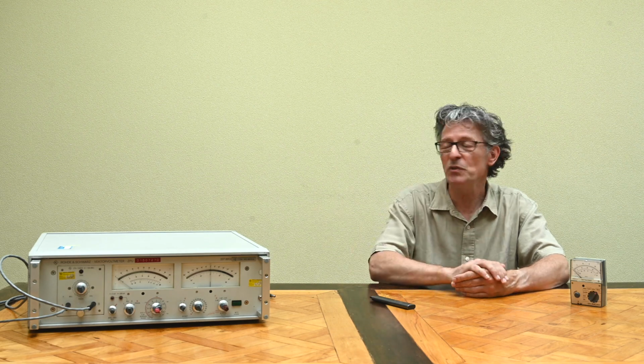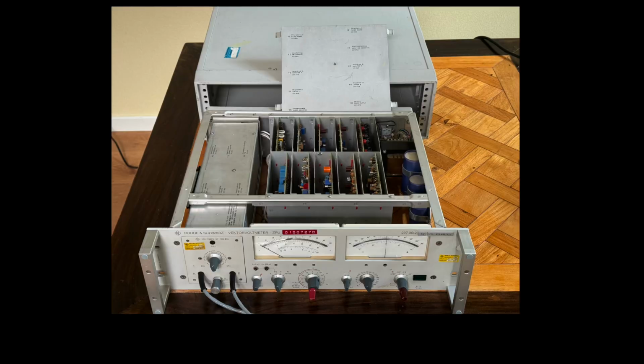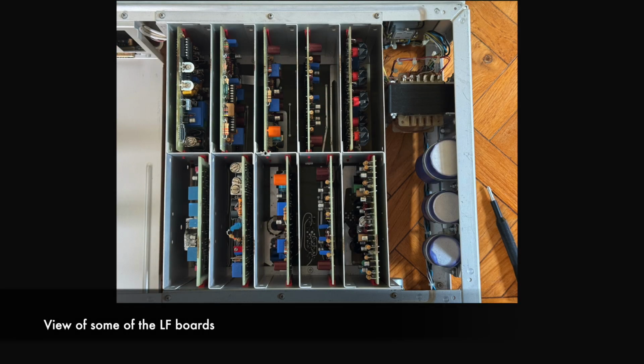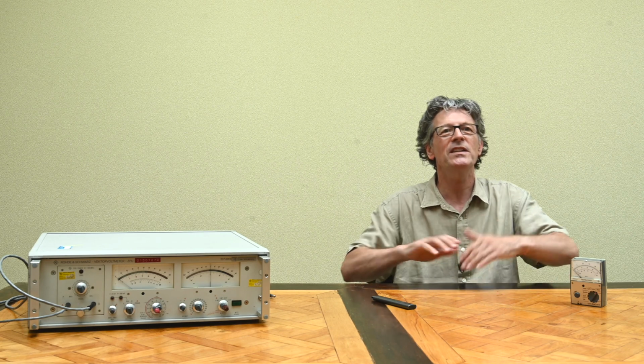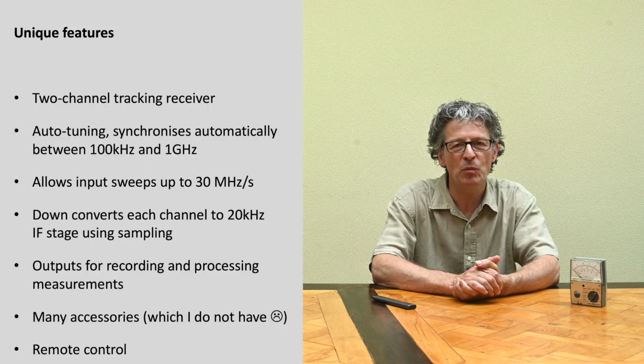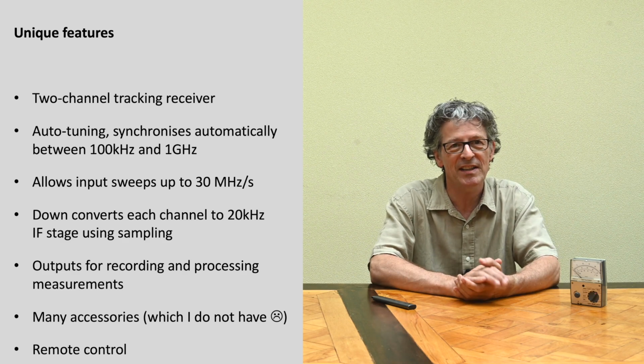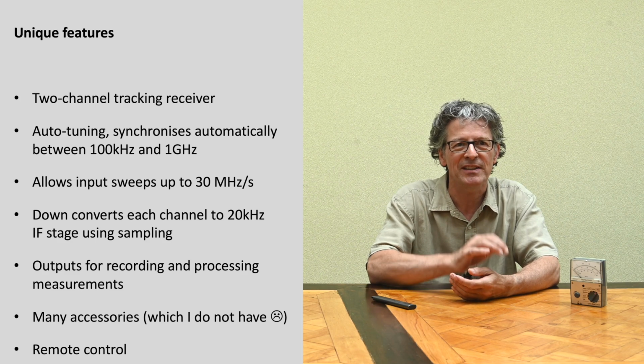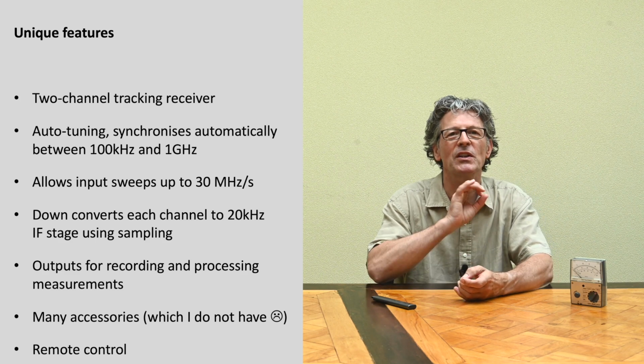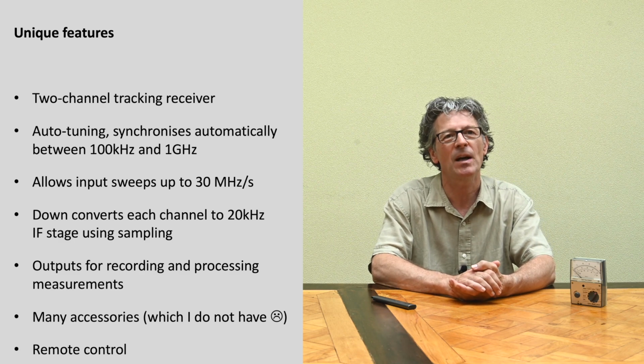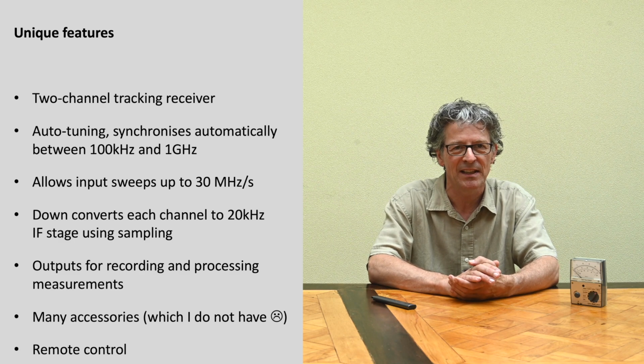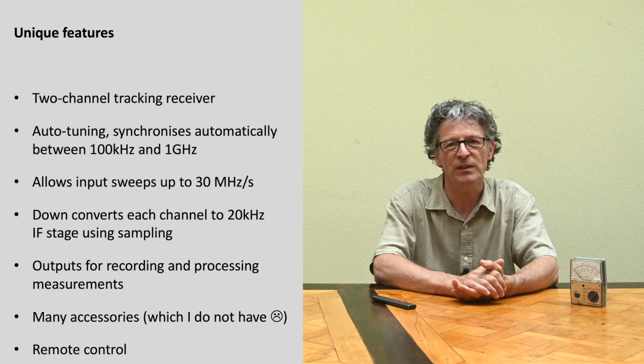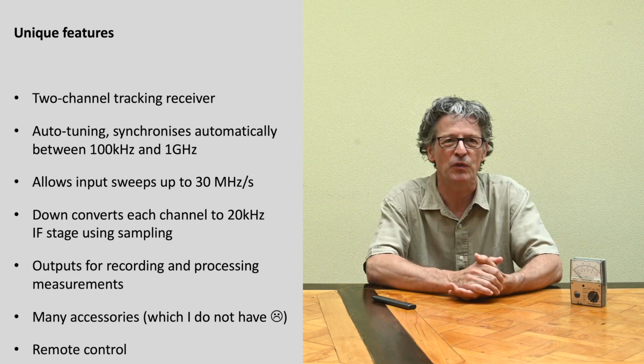Now, how does it do this? I'll show you in a moment a couple of pictures, actually quite full of equipment here. And let me just highlight some unique features. So what we have is a two-channel tracking receiver. We've got two fully identical channels that both go to 1 gigahertz, and the first channel is a tracking receiver which supports auto-tuning. So it synchronizes itself automatically to the incoming signal between 100 kilohertz and 1 gigahertz, but you have to set the range in decade steps, where it has to look for that signal.